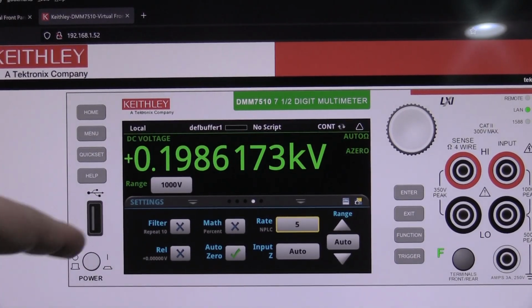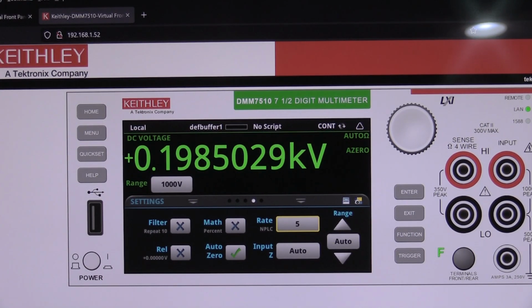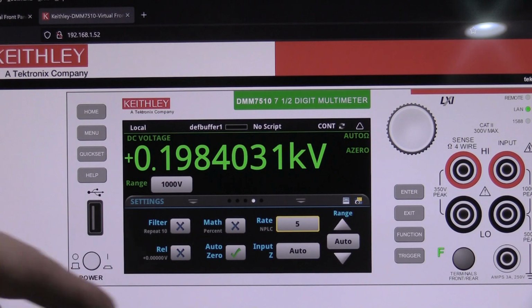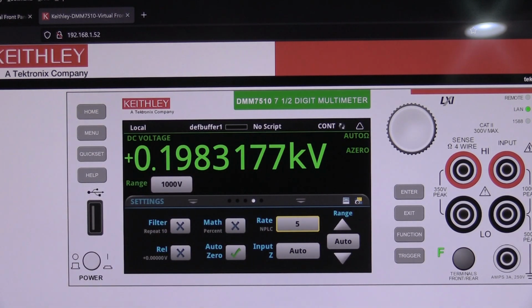Now I've moved the meter down to my 7510. I want a pretty fast rate on this one, so I'm going to let it kick over, but I don't want the charge to bleed off. We're actually watching the charge bleed off through the meter impedance right now, since we're not hooked up to the power supply anymore.